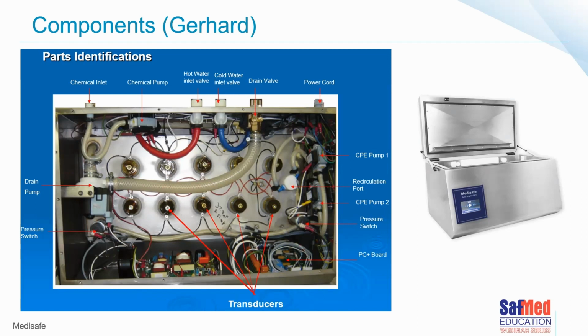So very often people say, but why should we service this machine? They can't really understand, there's not many moving parts. But the little pumps are very sensitive. They often get clogged with patient debris, especially if the staff using the machine haven't changed the small disposable filters. You can also see the pressure switches that control the pressure of the flow running through the instruments, which must be set at specific pressures. All of these parts need to be checked and cleaned during the service.